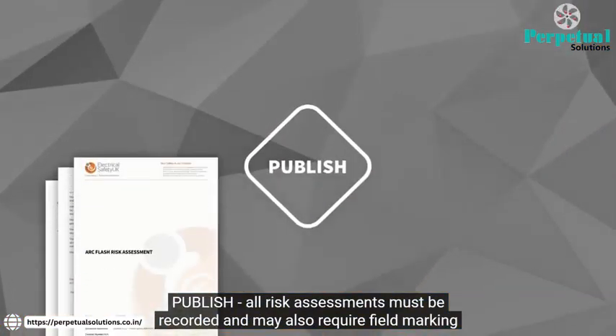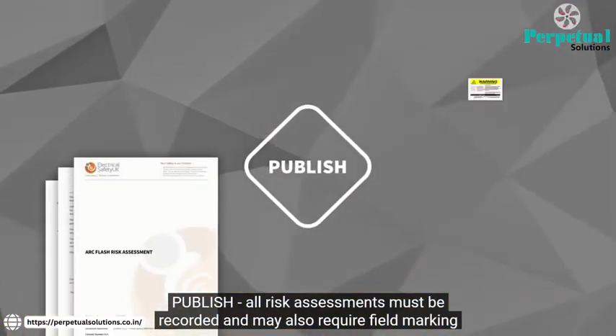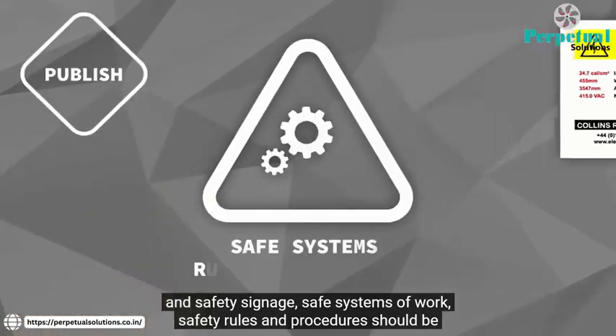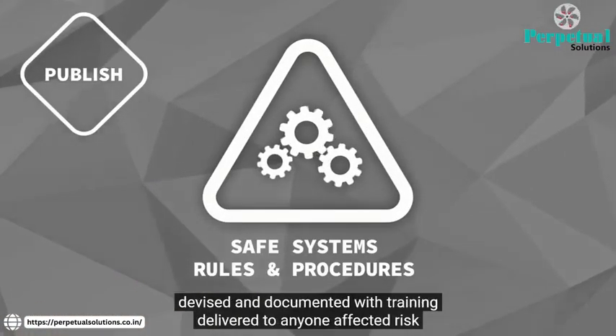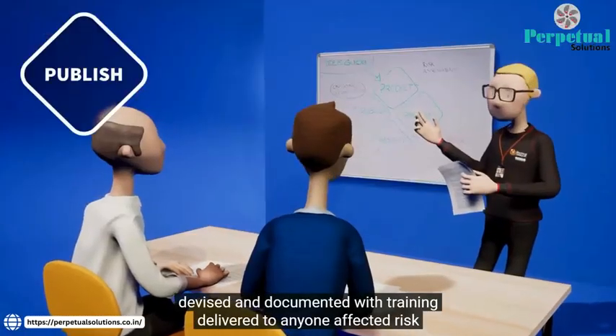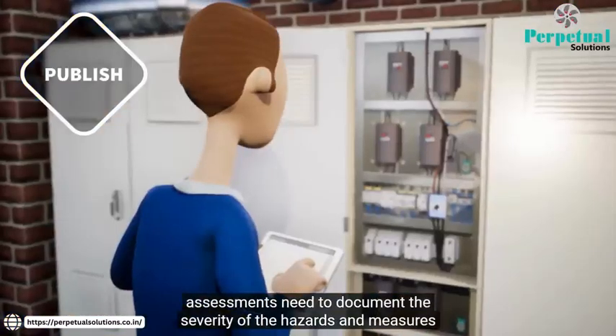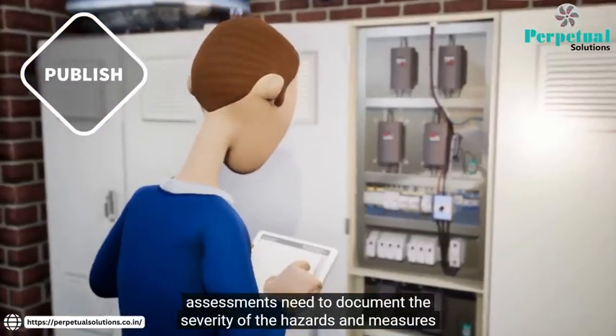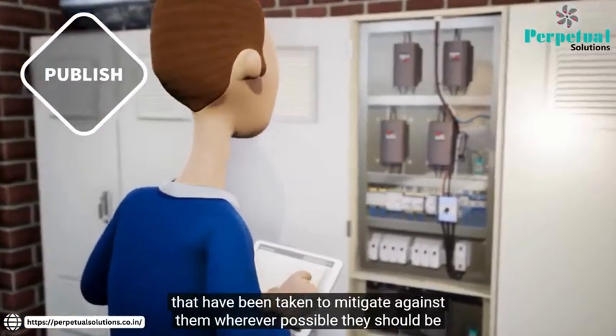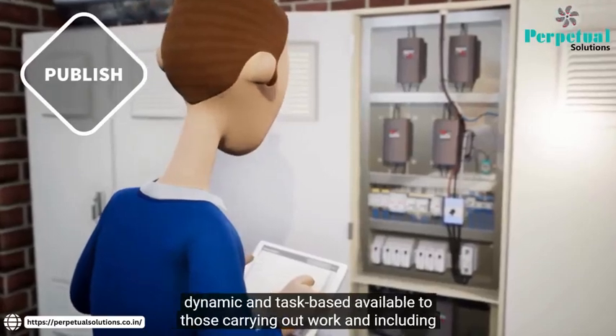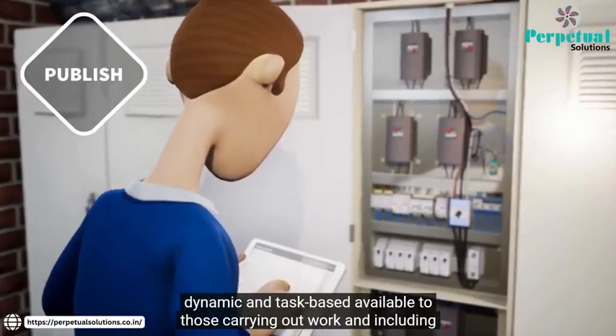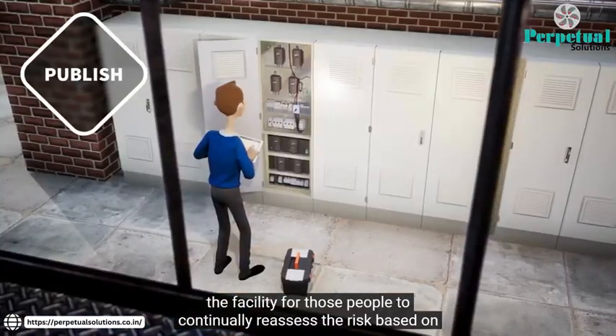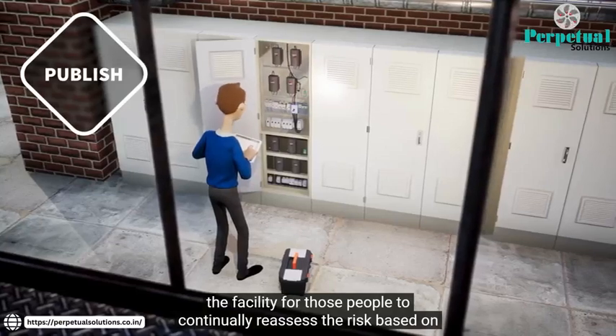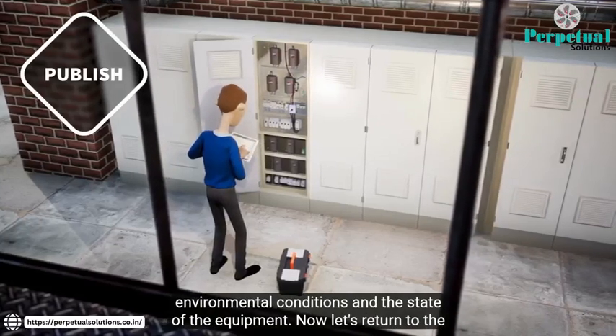All risk assessments must be recorded and may also require field marking and safety signage. Safe systems of work, safety rules and procedures should be devised and documented, with training delivered to anyone affected. Risk assessments need to document the severity of the hazards and measures that have been taken to mitigate against them. Wherever possible, these should be dynamic and task-based, available to those carrying out work, and including the facility for those people to continually reassess the risk based on environmental conditions and the state of the equipment.